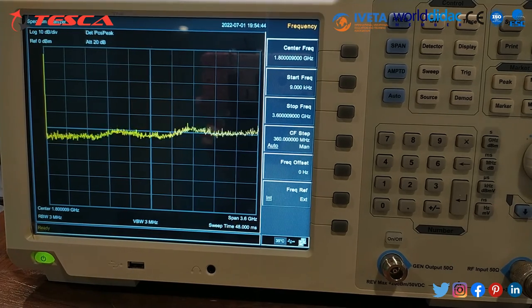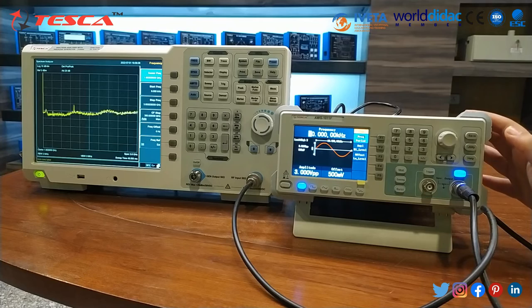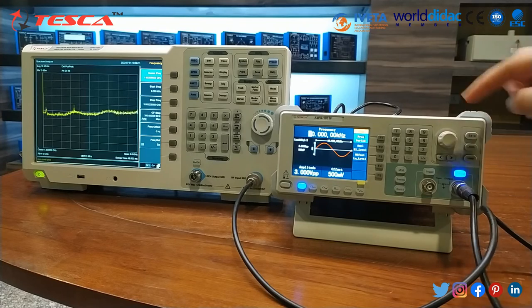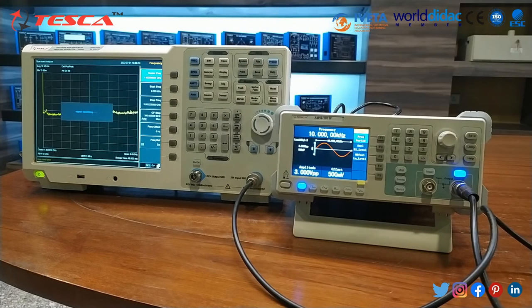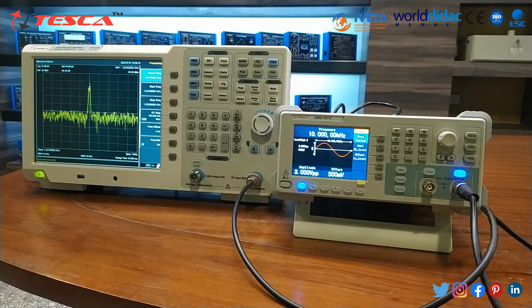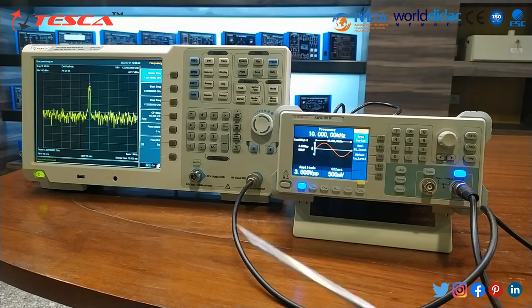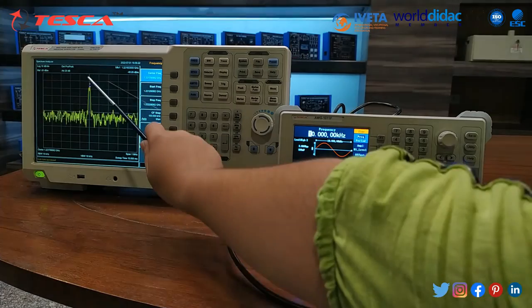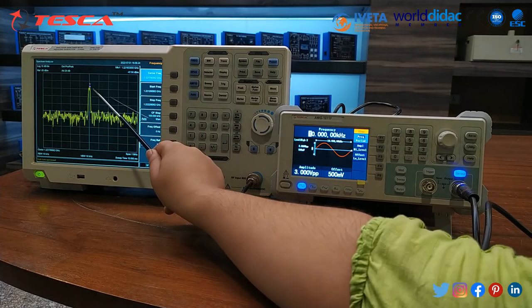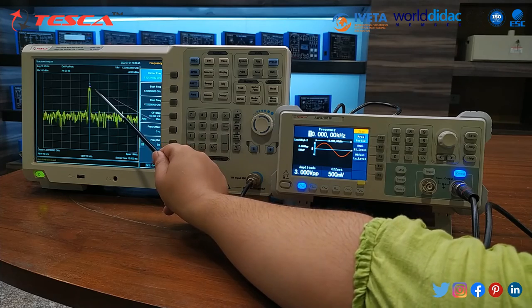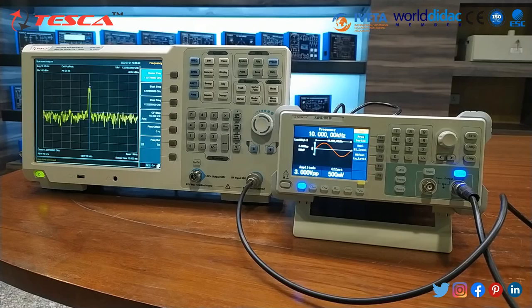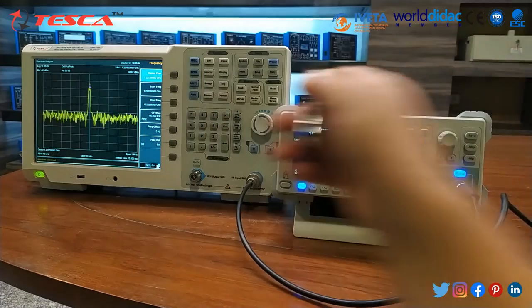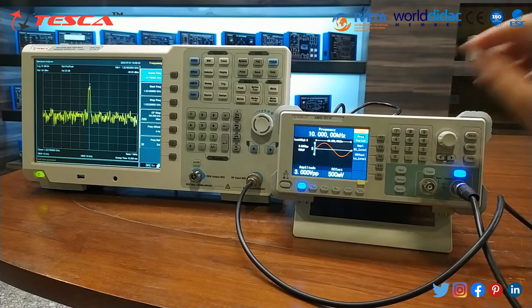Now we will generate the spectrum. Press the output button, then press the auto button. It will start searching the signal — wait a few seconds. You can see that the spectrum is obtained and the center frequency is now approximately 1.22 GHz.